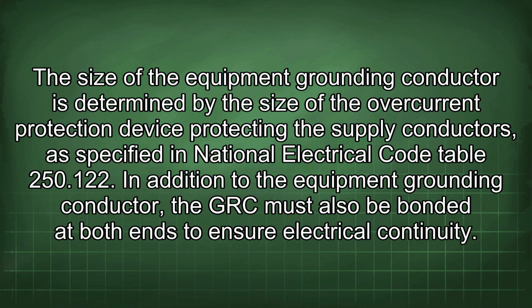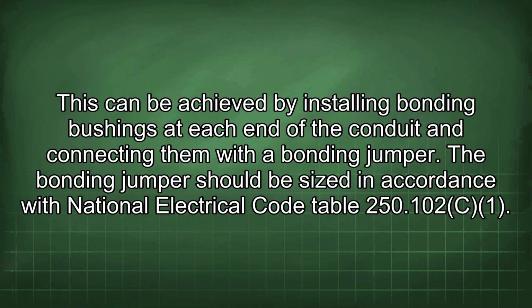The size of the equipment grounding conductor is determined by the size of the overcurrent protection device protecting the supply conductors, as specified in National Electrical Code Table 250.122. In addition to the equipment grounding conductor, the GRC must also be bonded at both ends to ensure electrical continuity. This can be achieved by installing bonding bushings at each end of the conduit and connecting them with a bonding jumper.